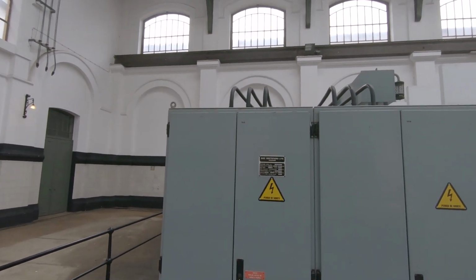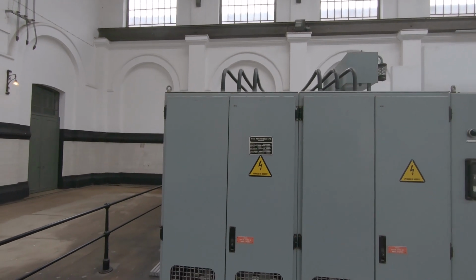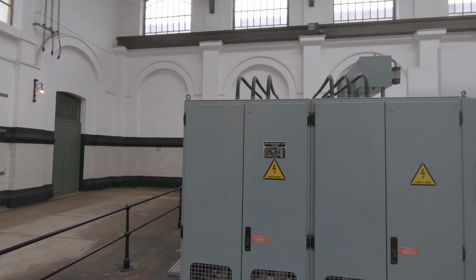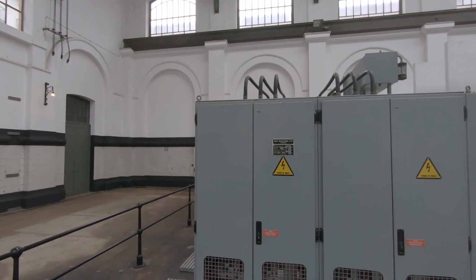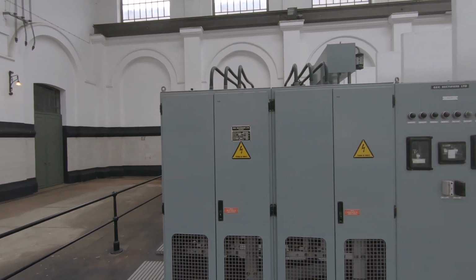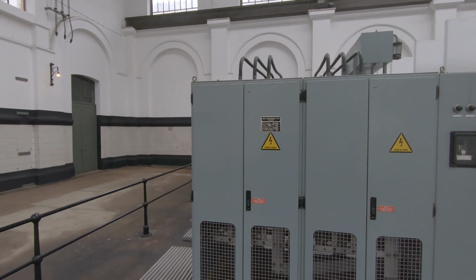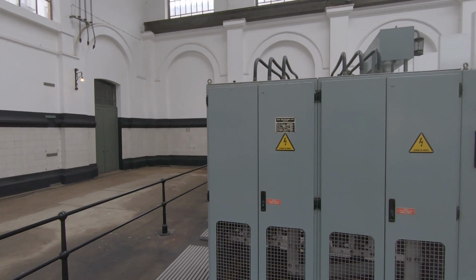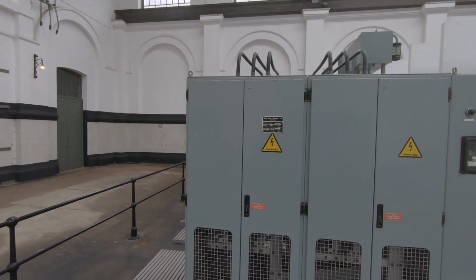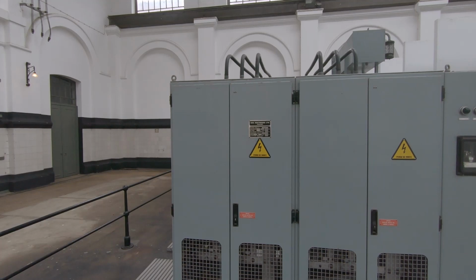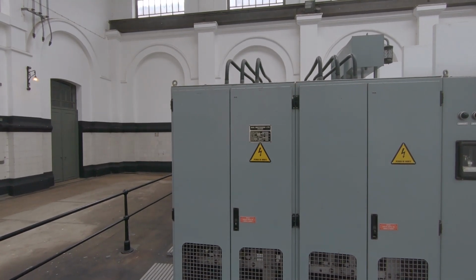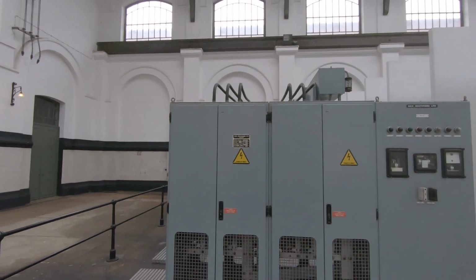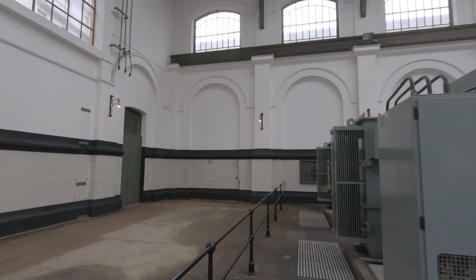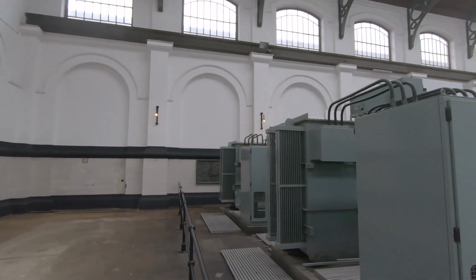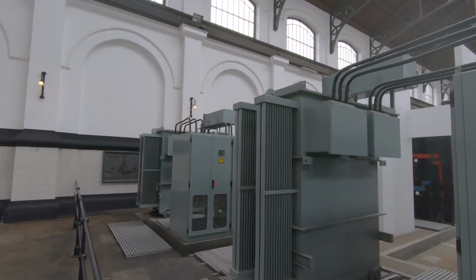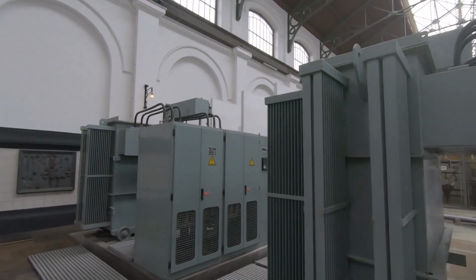There's a GE rectifier, 600 kilowatts, rated output 1044 amps at 575 volts. So the primary was 15,000 volts AC, 3-phase, 50 hertz. And the output was 575 volts - must be DC because that's what they said. So that's what a rectifier does - takes the 3 AC sine waves and converts it into a DC current.